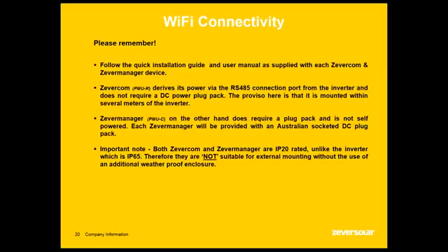Both ZeverCom and ZeverManager are not IP65 rated, they are IP20 rated. This means they are not suitable for external mounting without the use of a weatherproof enclosure, which as previously mentioned are relatively inexpensive and can be picked up from your local electrical wholesaler.